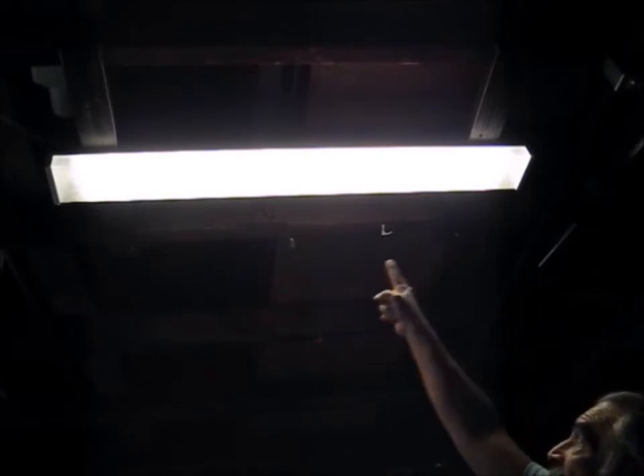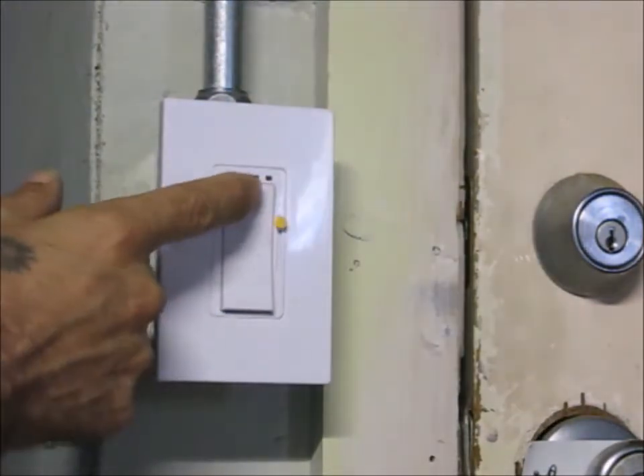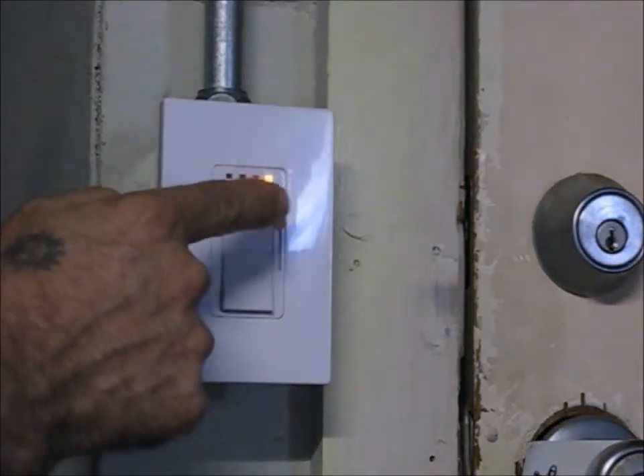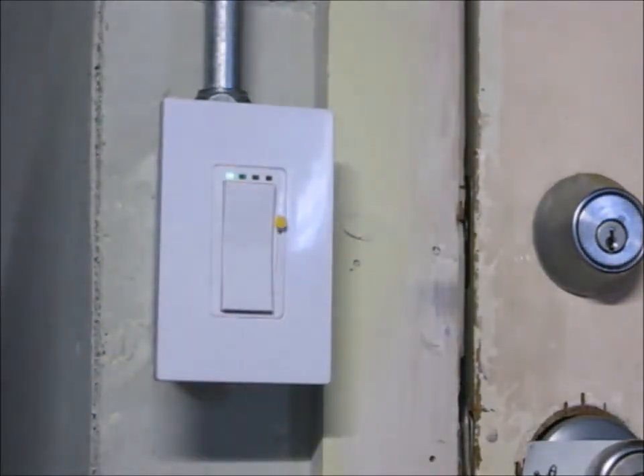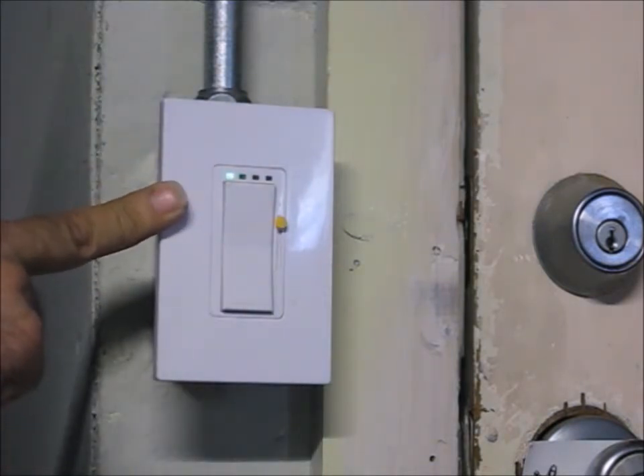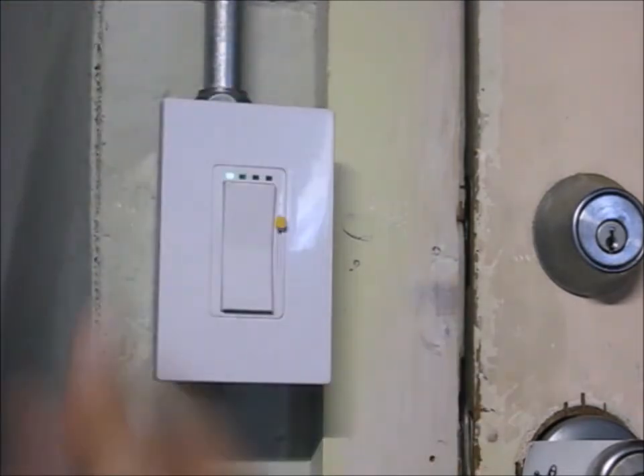Now what we have here is essentially the same thing we had on the benchtop. It's a Lumenergy ballast, this one takes T5s, and we have a control switch on the wall. So we have our DALI supply this time being produced by the ballast. This is kind of unique, it's a Lumenergy Fulham lamp. I'm just going to take readings off of it in the same manner because this is going to spit out the same commands as the one on our test set and then we'll average them out and look at them.